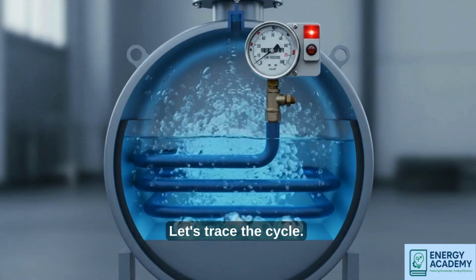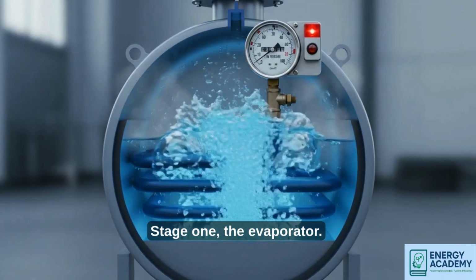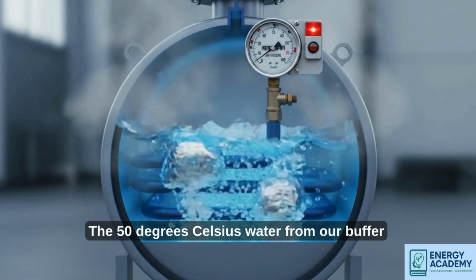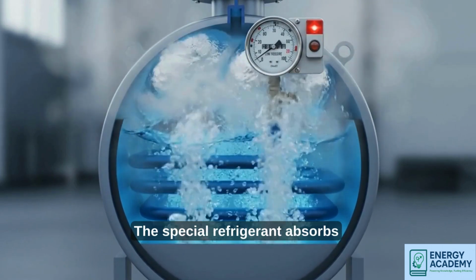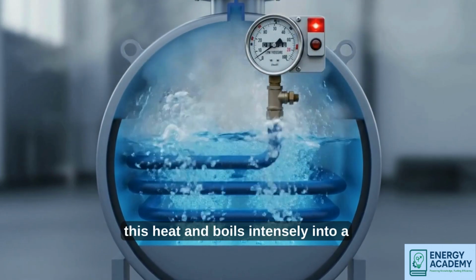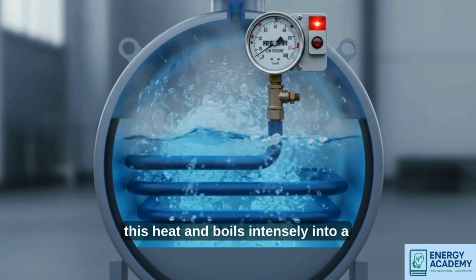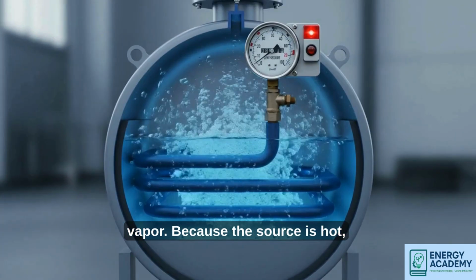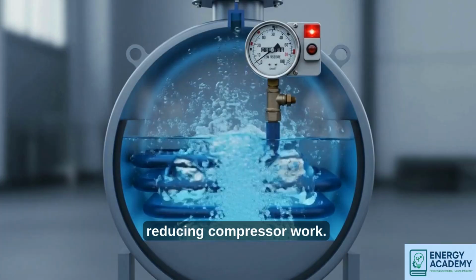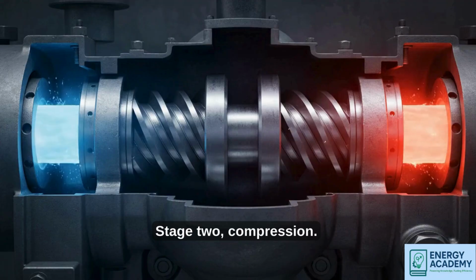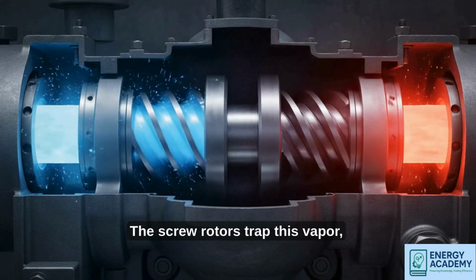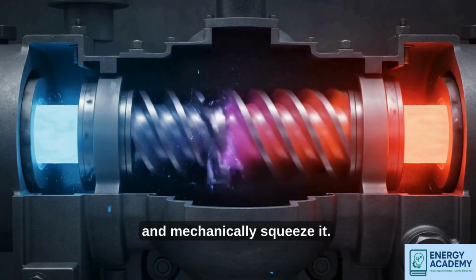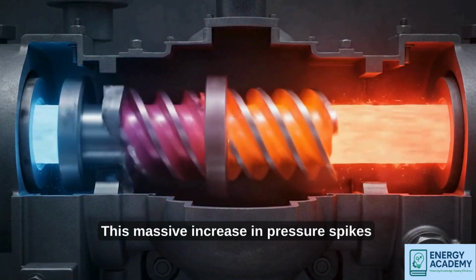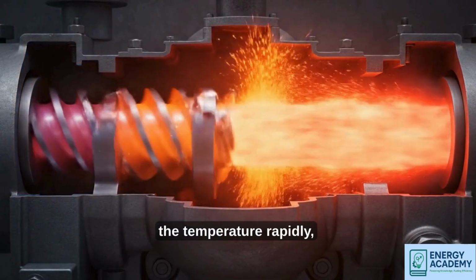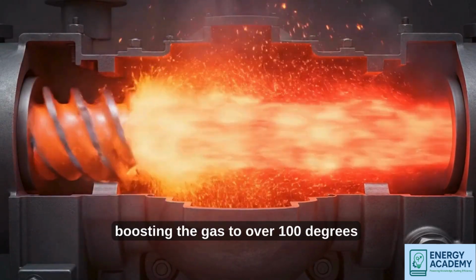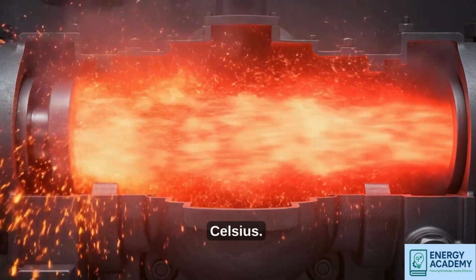Let's trace the cycle. Stage 1, the evaporator. The 50 degrees Celsius water from our buffer tank circulates here. The special refrigerant absorbs this heat and boils intensely into a vapor. Because the source is hot, the suction pressure remains high, reducing compressor work. Stage 2, compression. The screw rotors trap this vapor and mechanically squeeze it. This massive increase in pressure spikes the temperature rapidly, boosting the gas to over 100 degrees Celsius.